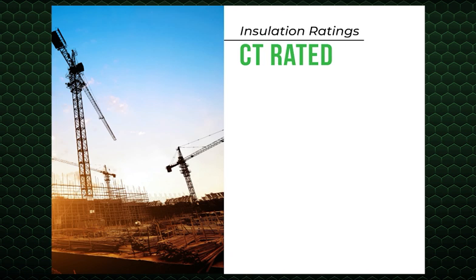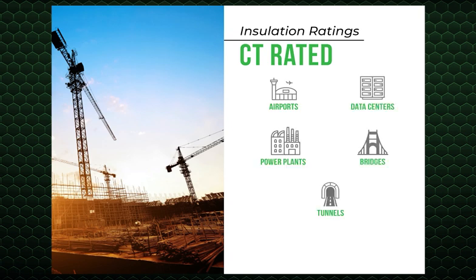CT rated refers to cable tray rated products. Products with this designation are suitable for use in overhead or open air cable tray and vertical trays. CT rated cable applications primarily include commercial facilities like airports and data centers, and industrial settings like power plants, bridges, and tunnels. Service wire's XHHW insulated single conductors 1/0 and larger are CT rated for 600 volt/1 kV. For designated grounding or bonding conductors, the NEC allows 2 gauge and larger for tray cable use. CT rated single conductors are primarily used in heavy commercial applications.